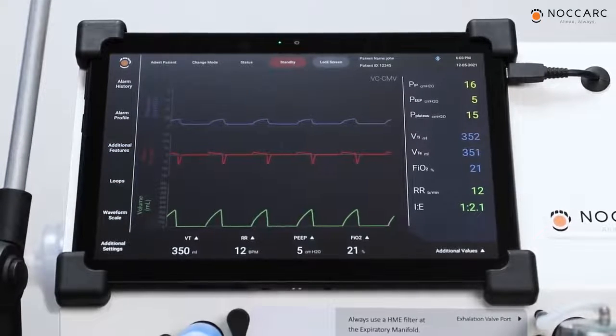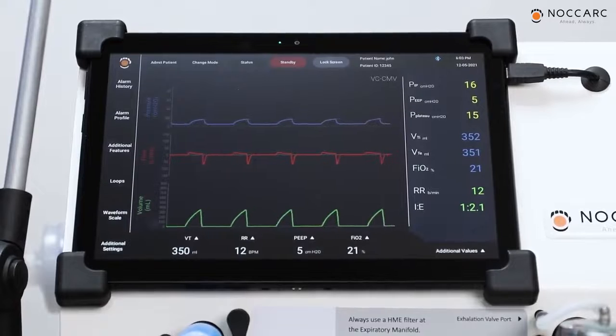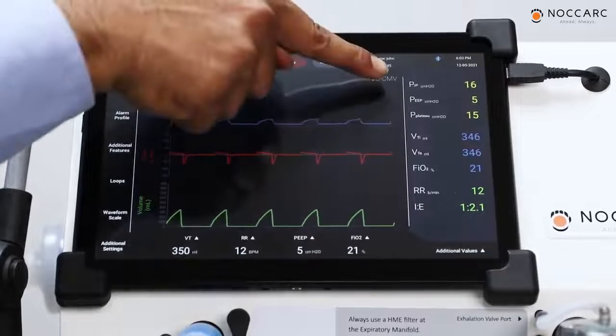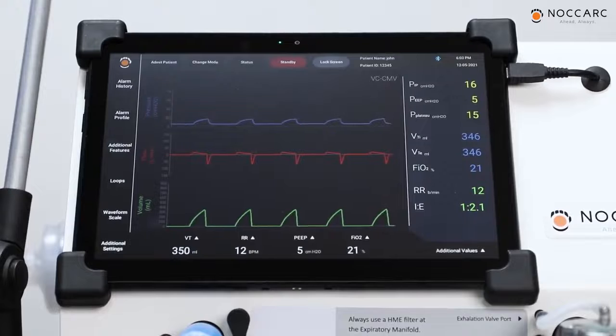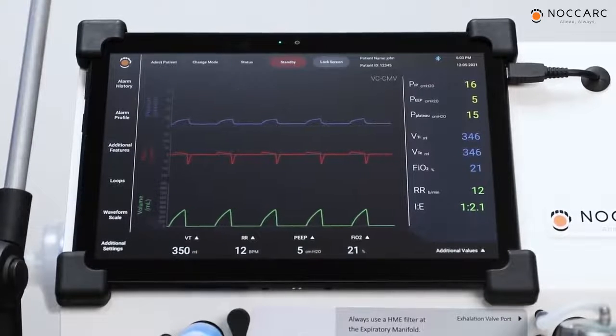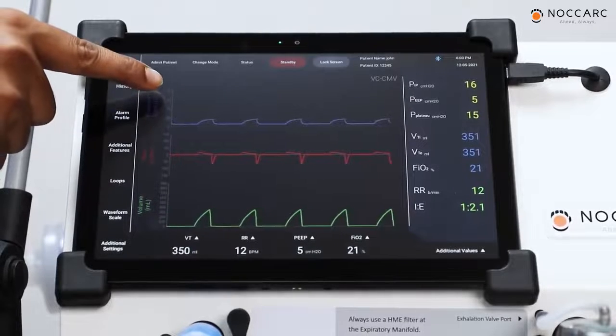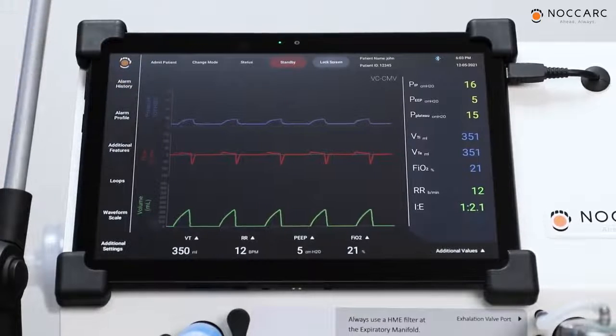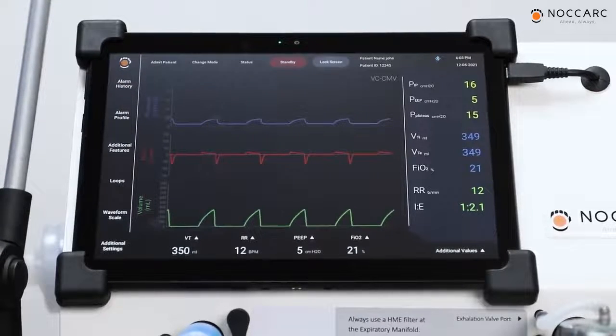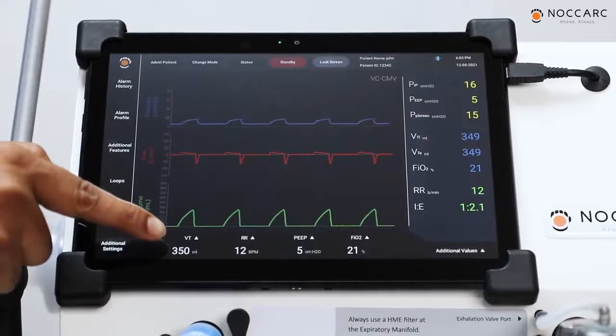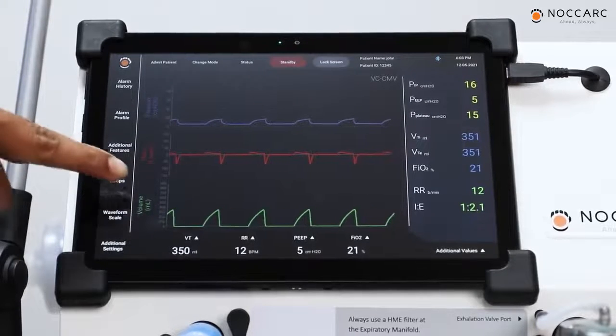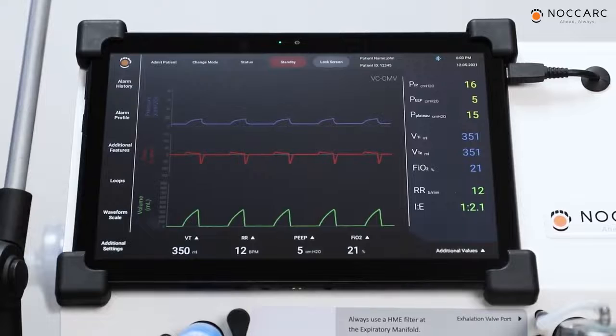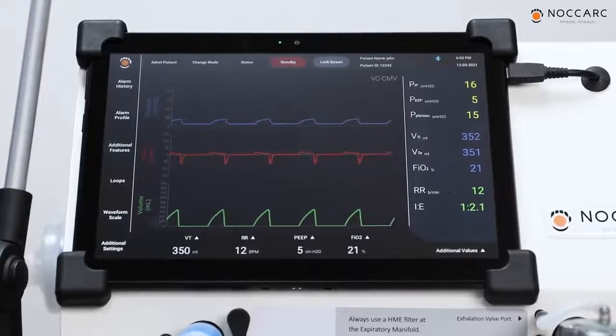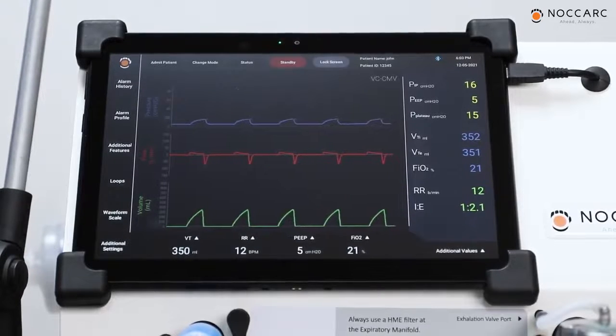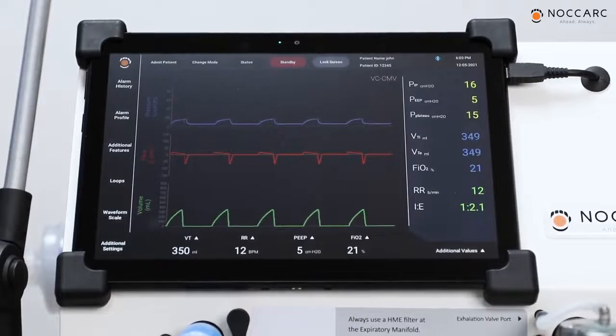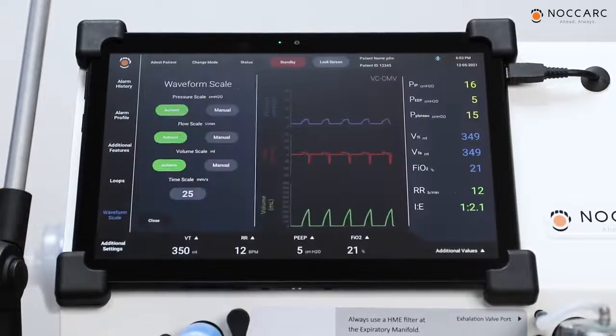Next feature provided by company is waveform scale. If you look at PIP, that is peak inspiratory pressure, is 16, but in the waveform scale the pressure graph is up to 80. Similarly, targeted volume is 350, but in the graph it is showing up to 800. To observe graph on maximize scale, press on waveform scale.